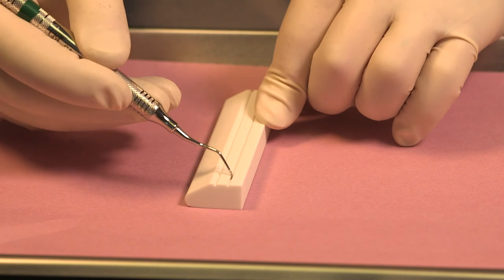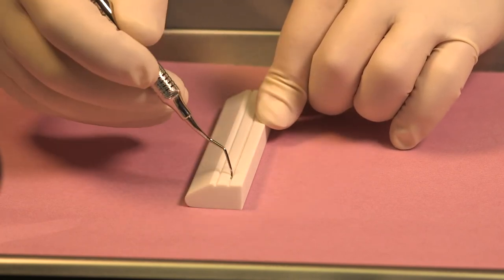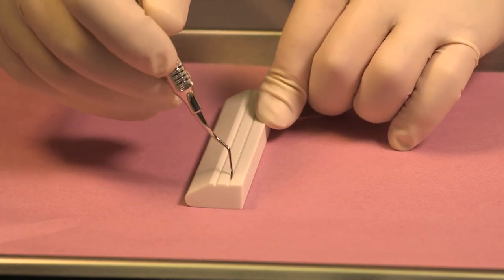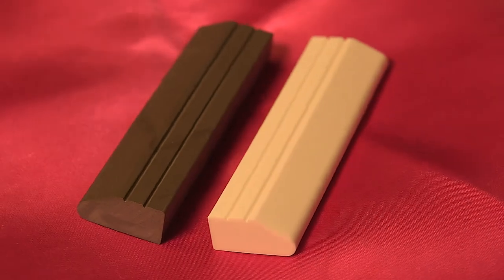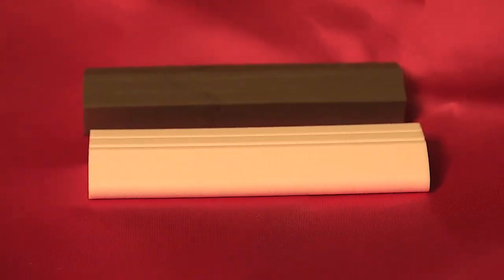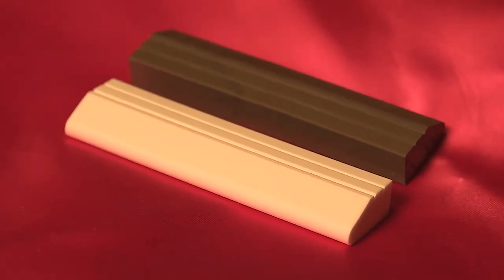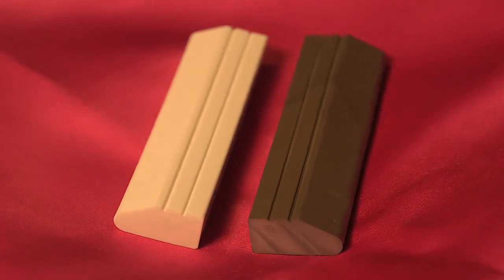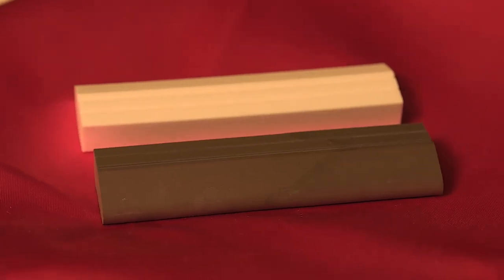Following sharpening with the chocolate honing channel sharpening stone, we recommend always finishing with the finer white honing channel sharpening stone to provide the smoothest and sharpest cutting edges. The channels of the white and chocolate honing channel sharpening stones are curvilinear and geometrically the same, and are designed to follow, where possible, the written suggestions of the International Standards Committee on Dental Curette and Scaler Instrument Designs.